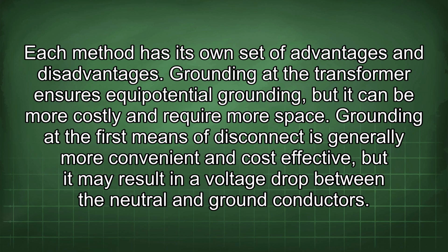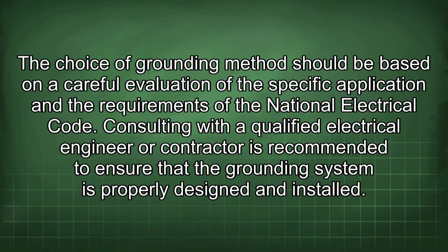Grounding at the transformer ensures equipotential grounding, but it can be more costly and require more space. Grounding at the first means of disconnect is generally more convenient and cost-effective, but it may result in a voltage drop between the neutral and ground conductors. The choice of grounding method should be based on a careful evaluation of the specific application and the requirements of the National Electrical Code. Consulting with a qualified electrical engineer or contractor is recommended to ensure that the grounding system is properly designed and installed.